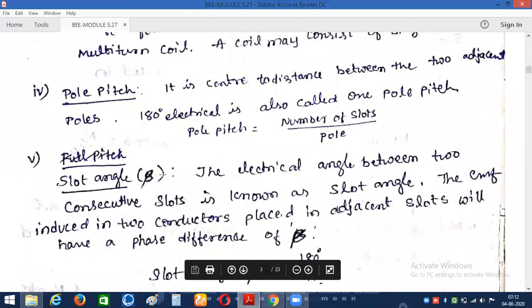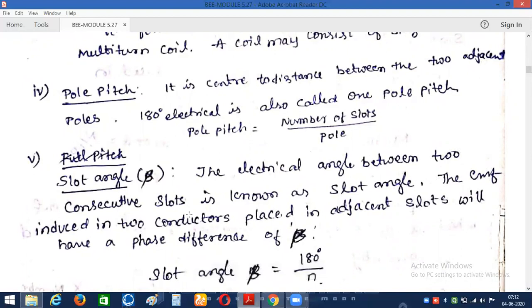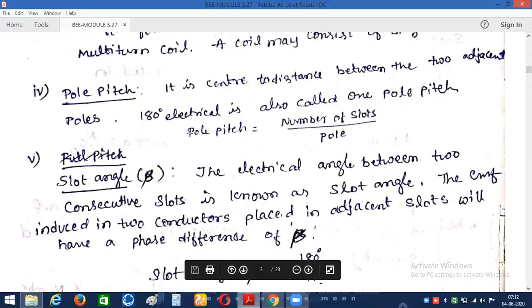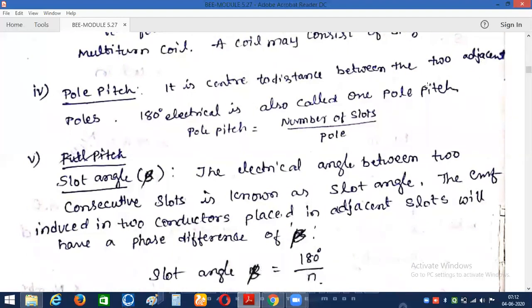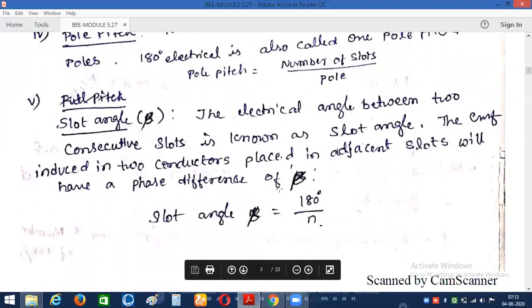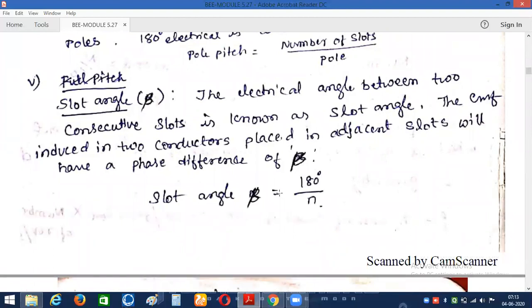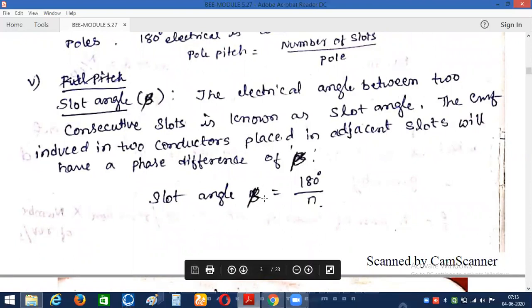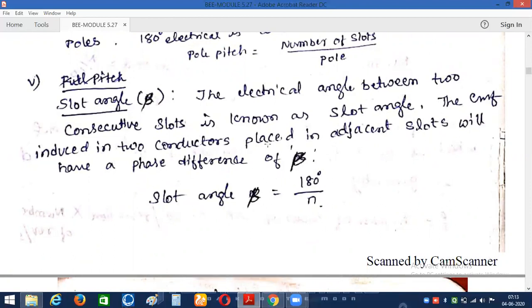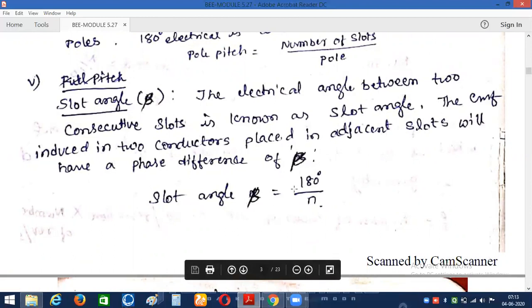Next: pole pitch. Pole pitch is the center-to-center distance between two adjacent poles, which is usually 180 degrees electrical, and is also called one pole pitch of the given machine. Next: slot angle. Slot angle is the electrical angle between two consecutive slots — the electrical angle between the north pole and south pole (two consecutive poles). The EMF induced in two conductors placed in adjacent slots will have a phase difference of beta, and the slot angle beta is calculated by 180 degrees divided by N (number of slots per pole).